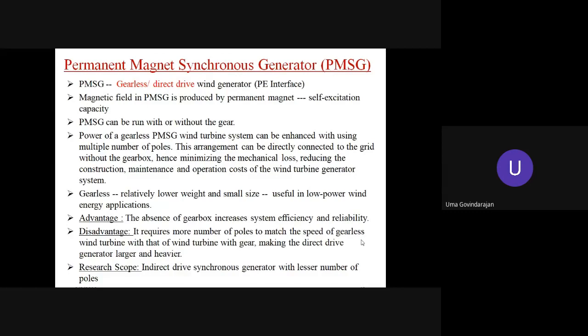PMSG can be run with or without gear, but predominantly it is adopted only for its gearless operation. So, okay, the power of a gearless PMSG wind turbine system can be enhanced by using a multiple number of poles. Make a large machine with more poles, and we can increase the speed of the machine. This arrangement can be directly connected to the grid without the gearbox, hence minimizing the mechanical loss and reducing the construction, maintenance, and operation cost of the wind turbine generator system.